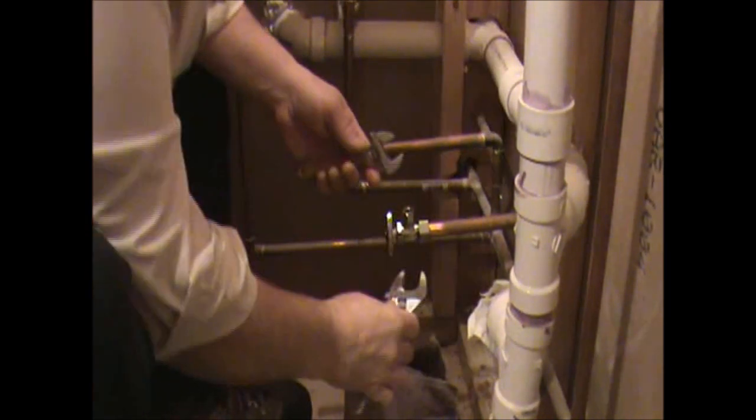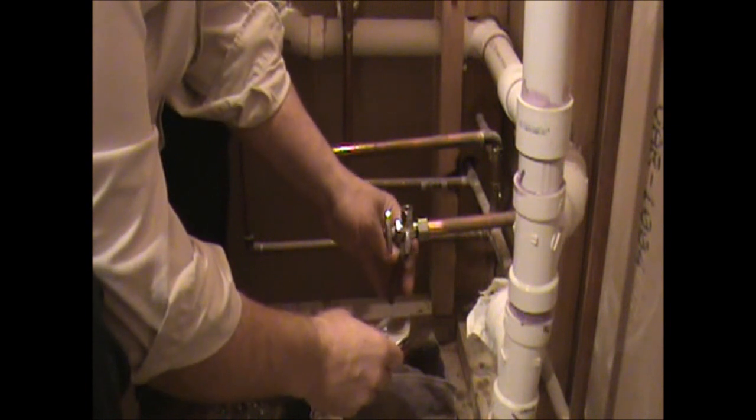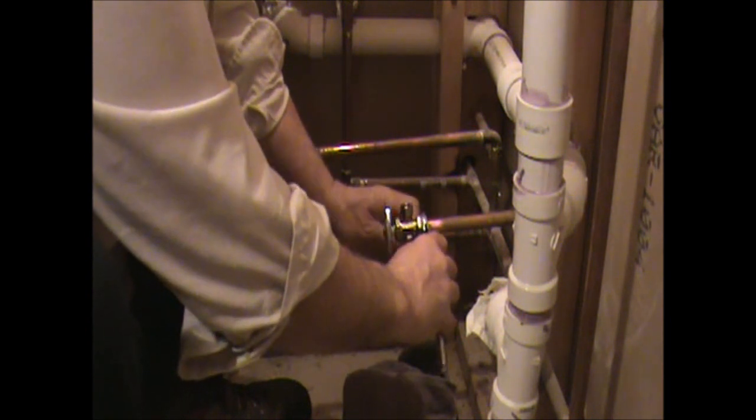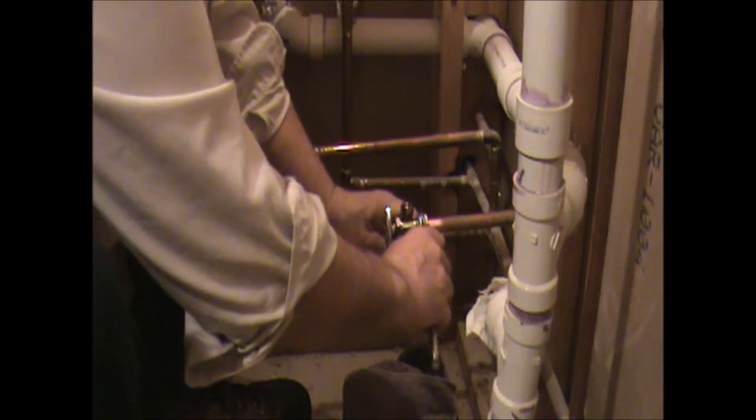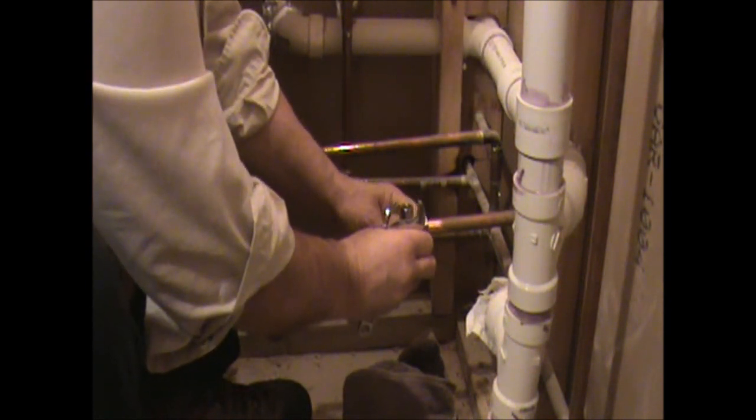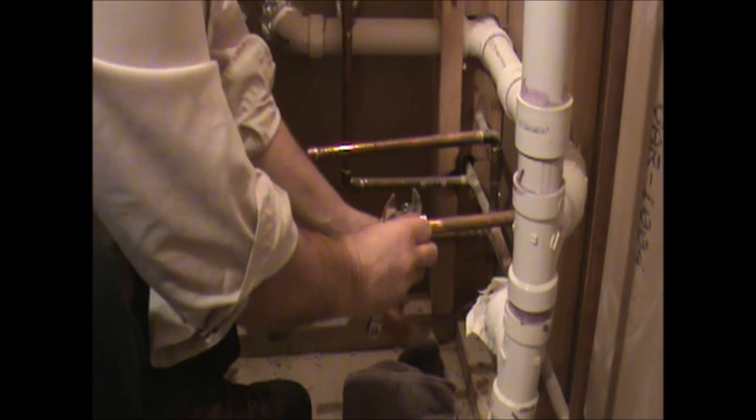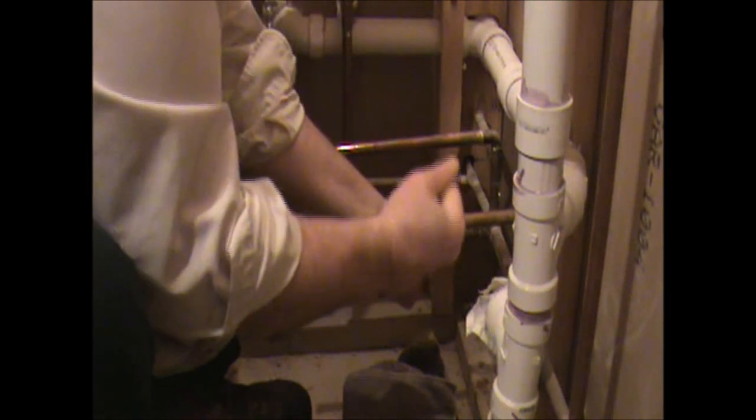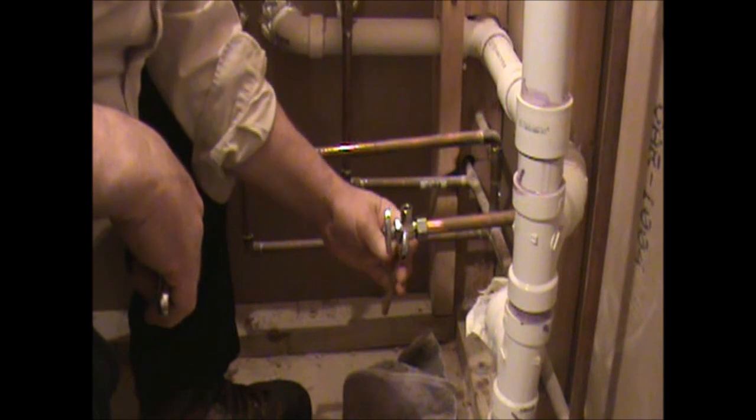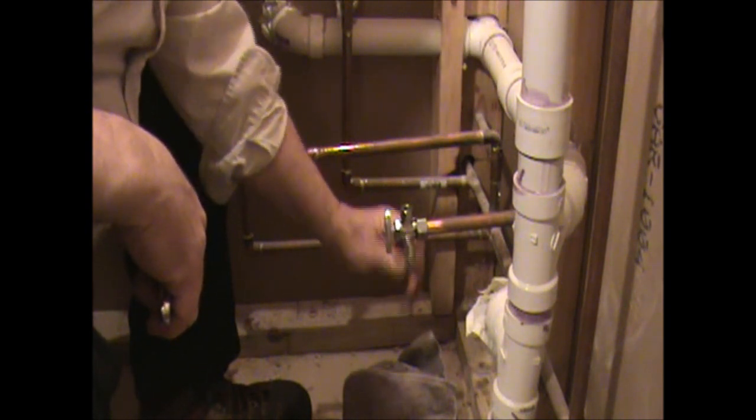So what you're going to do now is you're going to tighten it up, a couple of crescent wrenches. Now you always want to back this up. When I say back it up, you want to hold the valve itself while you're tightening it up. And it doesn't take a whole lot to tighten this up. Squeeze that bushing in there. And like I said, you don't want to tighten it too much. Just get it snug and then stop. Like I said, you can always tighten up a little bit more if you need to.